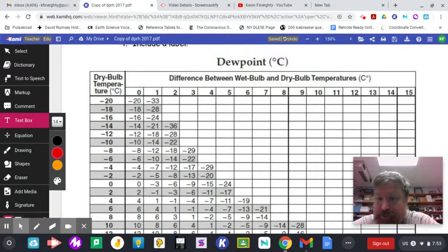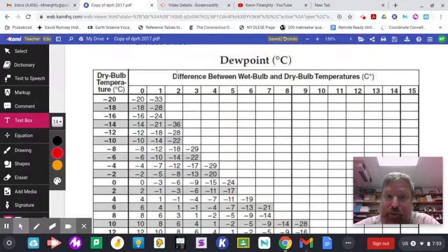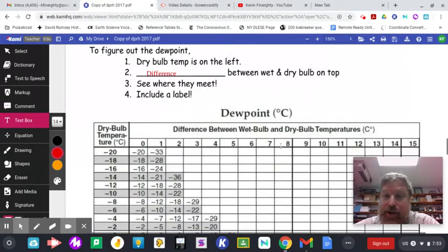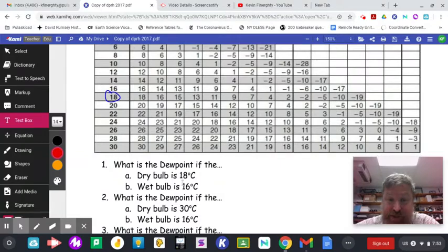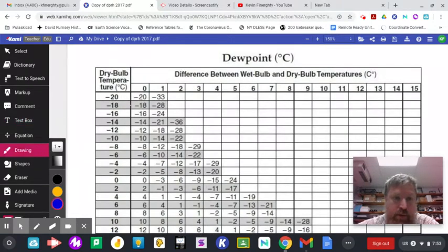I like you. I'm glad you're here with me, but you didn't watch the video. We don't need the wet bulb number. We need the difference between wet bulb and dry bulb. So if I come down here, the difference subtracting between 18 and 16 is 2. So that's what I need. And again, it's your call, I suppose, but writing on these things tends to be the way to do it.